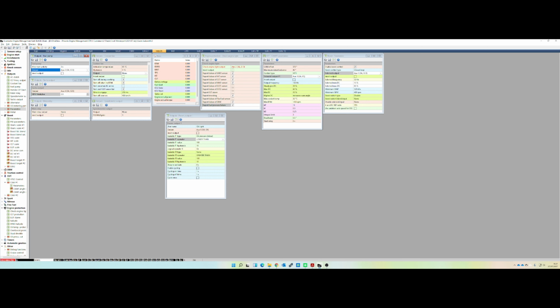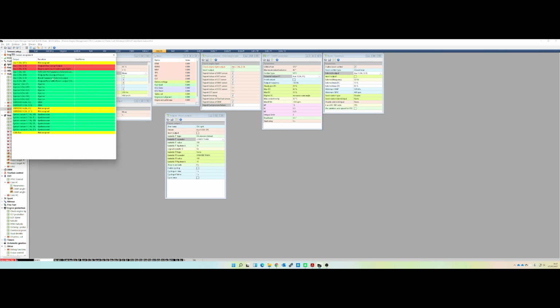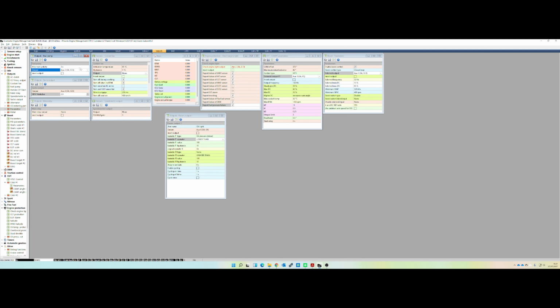Another way to figure that out is if you go to Show Assigned Outputs, you'll see there that two auxiliary 2s are assigned - one is output for fuel pump, one is engine protection light. So let's just change that back. It will warn you if you try to set it to something that's already there, and then you can either change the other one if it's in the wrong place, or change this one. Okay, so that's auxiliary 1.